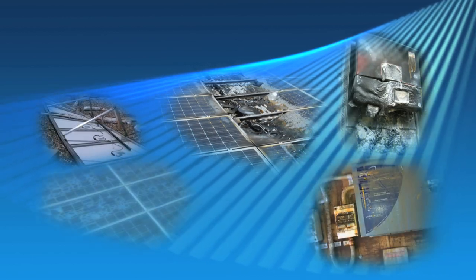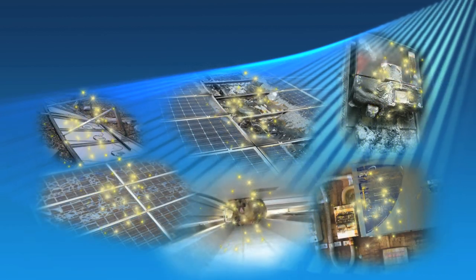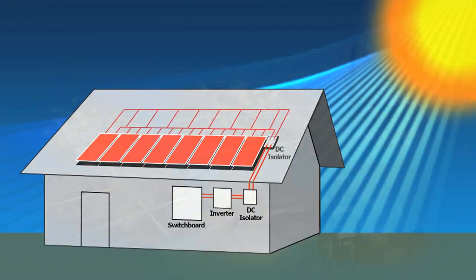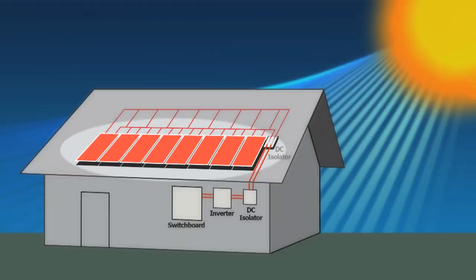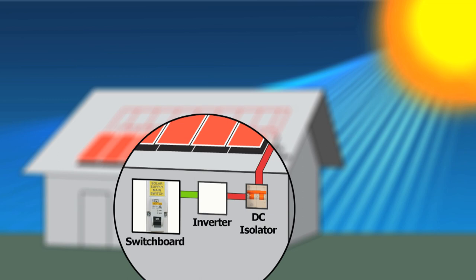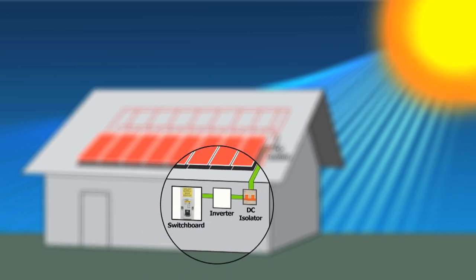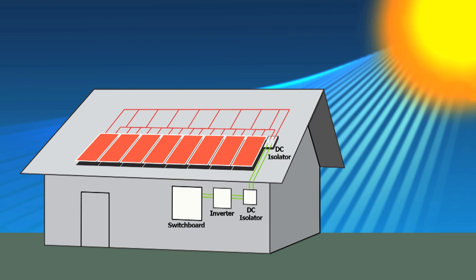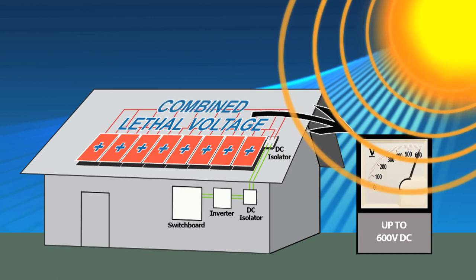One of the most pressing issues involves the safe isolation of these systems. Currently, the standard practice for the isolation of solar panels is to switch off the incoming AC supply and then turn off the DC isolator. Even by following this procedure, lethal voltage is still being generated throughout the panels, up to 600 volt DC, whenever the sun is shining.